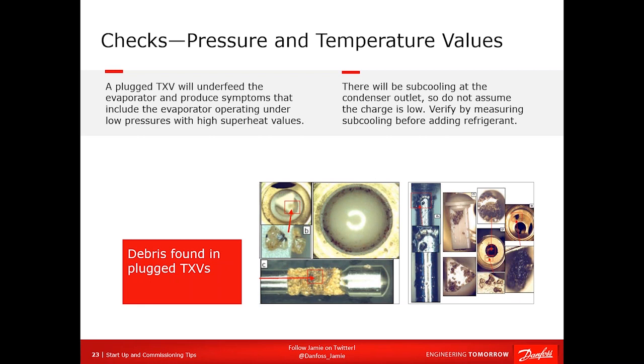Another thing, the stem in the middle, it looks like it's a cat paw. That is actually hole marks that are drilled in the valve stem by leftover grit from sandpaper or emery cloth. It breaks off, it gets in there, and when the refrigerant swirls around, it drills right in there like a drill, and it can cause all kinds of problems.